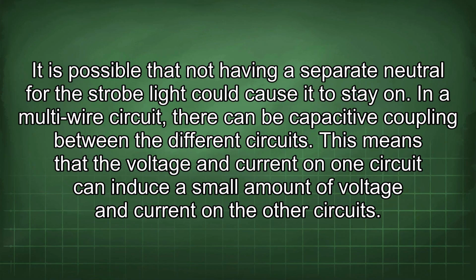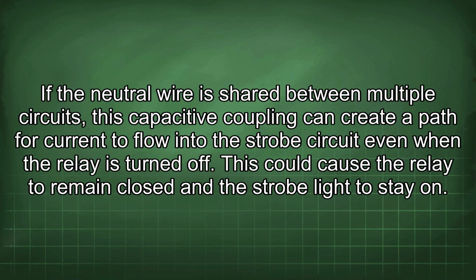It is possible that not having a separate neutral for the strobe light could cause it to stay on. In a multi-wire circuit, there can be capacitive coupling between the different circuits. This means that the voltage and current on one circuit can induce a small amount of voltage and current on the other circuits. If the neutral wire is shared between multiple circuits, this capacitive coupling can create a path for current to flow into the strobe circuit even when the relay is turned off.